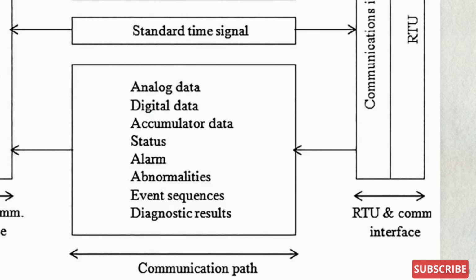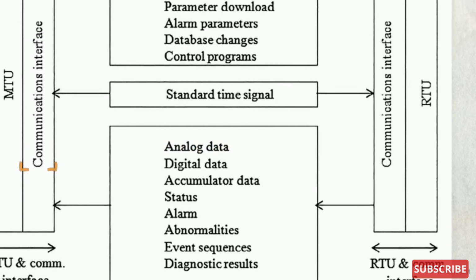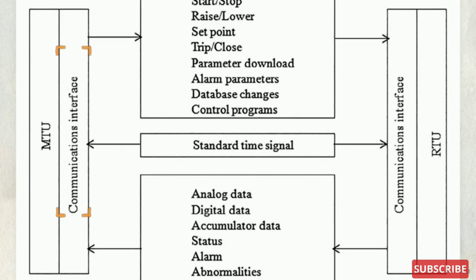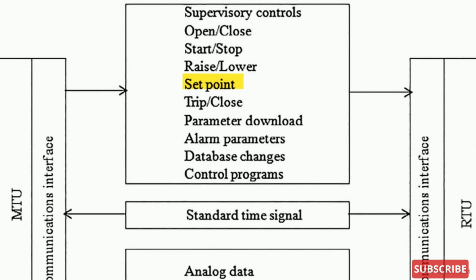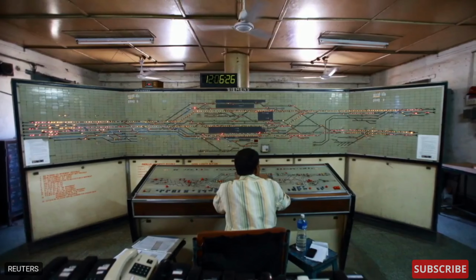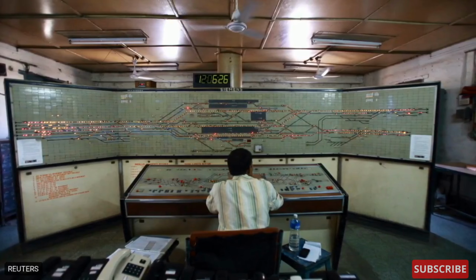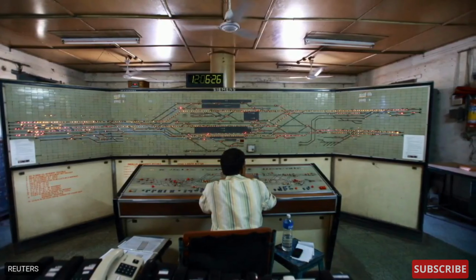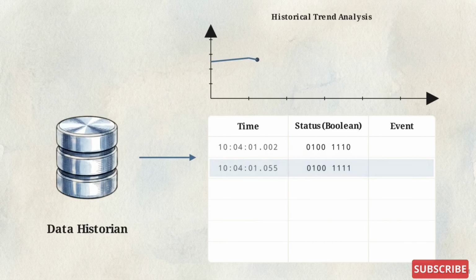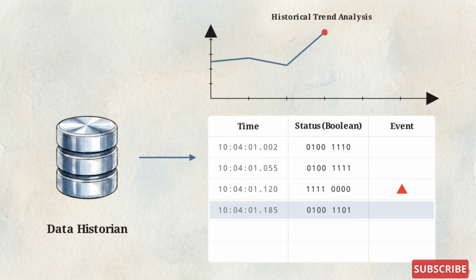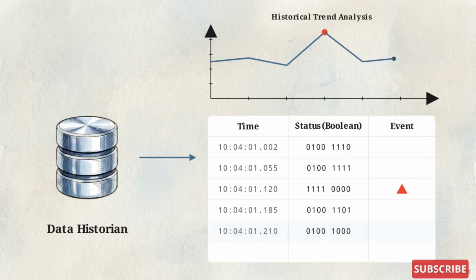Let's trace a single data point. An RTU reads an analog voltage from a field sensor, digitizing it. This data pushes upward through the communication interface to the MTU. The MTU instantly evaluates it, determining whether to trigger an alarm or adjust a set point. That raw telemetry is then routed to the human-machine interface, rendering it into an actionable, graphical mimic diagram for the operator watching the screens. Simultaneously, the data historian timestamps and archives this continuous stream of Boolean events and alarms, building a database for long-term trend analysis.